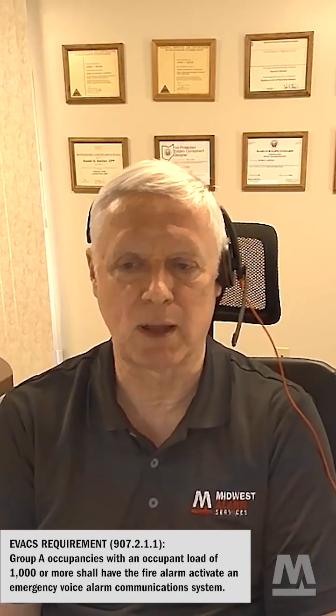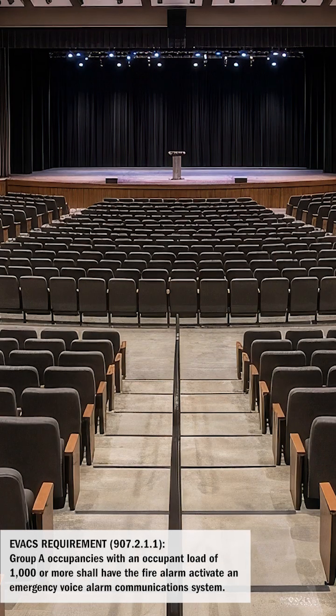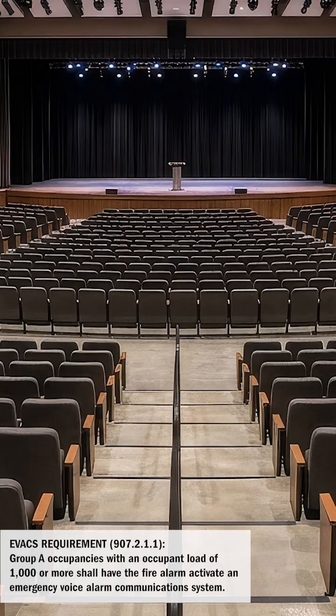We also get into more exotic forms of the fire alarm system when the occupancy goes above 1,000. So if you've got a Group A occupancy with an occupant load of 1,000 or more, typically a theater or a concert hall will exceed 1,000 occupants.